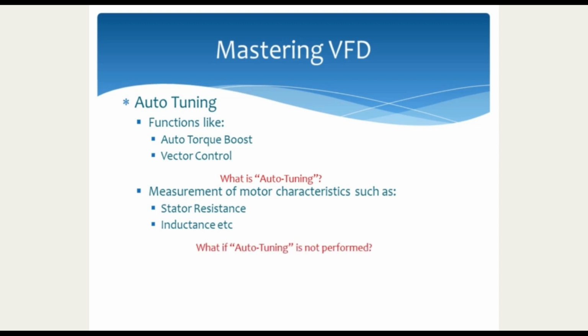And a final question: what if I don't do auto-tuning and use the functions mentioned? What will happen? The answer to that is the performance won't be good and could be even worse, which might create mechanical stress or an underperforming motor. So special care must be given to the functions which require auto-tuning.